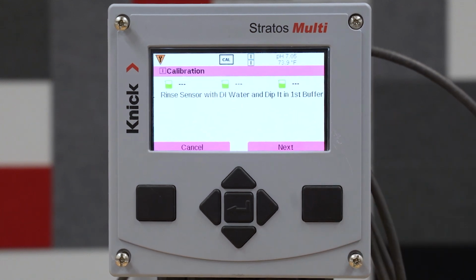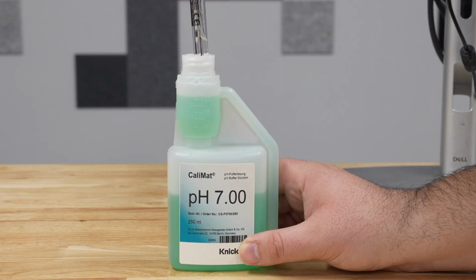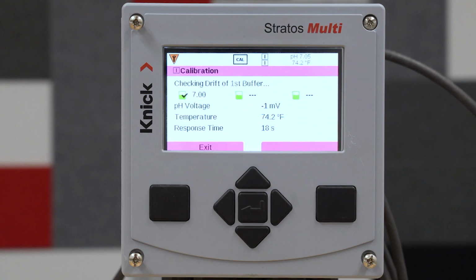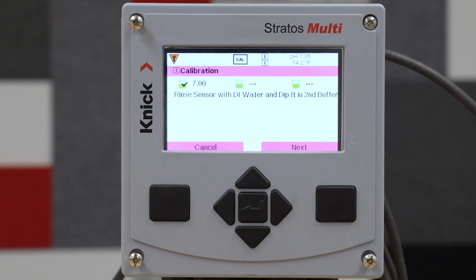At this point, you want to rinse your sensor with some deionized water and then dip it into the first buffer. The transmitter will pick up that the sensor is currently in the 7 buffer, and when it's ready, you can move on to the next.